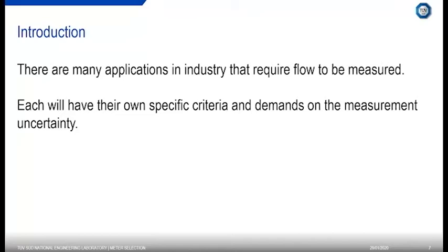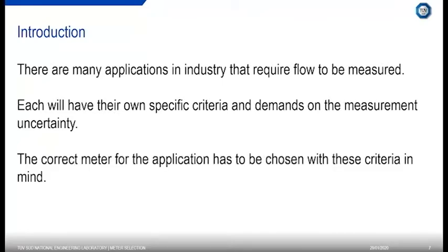Measurement uncertainty is a term many of you may know — essentially it relates to accuracy, i.e., how good a measurement you're looking for. If you have a high-value product such as oil or a pharmaceutical product, you want it measured with very low uncertainty to minimize errors. Different applications will have different measurement uncertainty requirements, and that has to be taken into account when picking a flow meter. There's no point picking the best meter if you don't need the best measurement uncertainty, and vice versa.